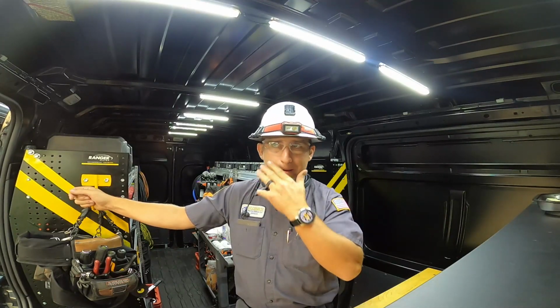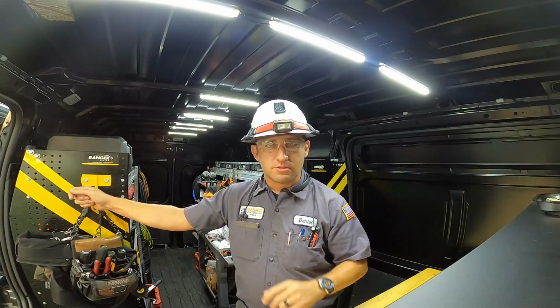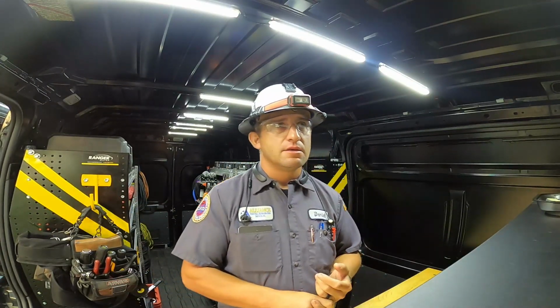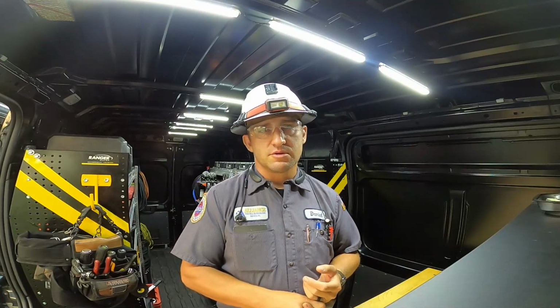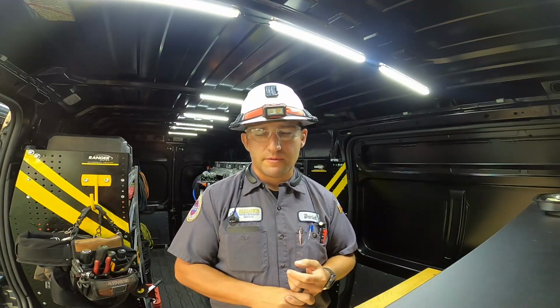So we're in here. We put in two brine heat exchangers, 3 compressors. We have 2 screws, a 300 horsepower screw and a 250 horsepower screw that has a VFD on it, and we have a recip too. The recip had some motor issues in the startup, so the motor is being sent out right now. We sent it out yesterday, and we're getting it repaired.